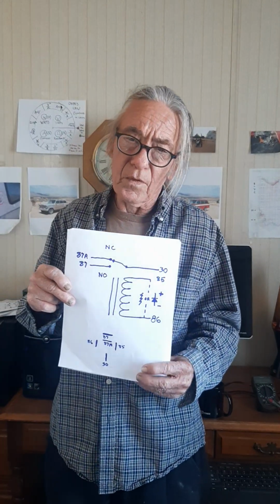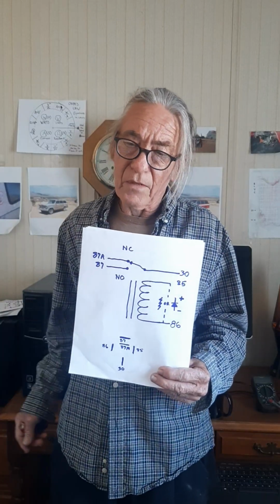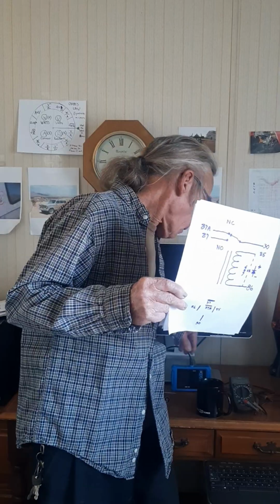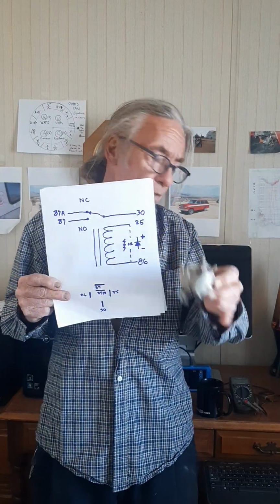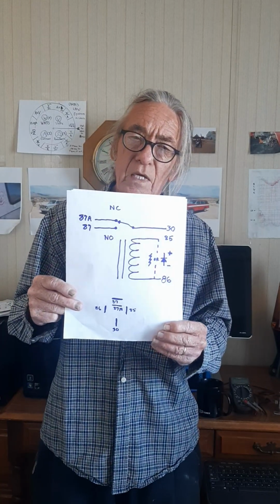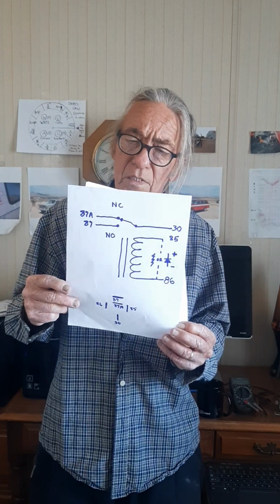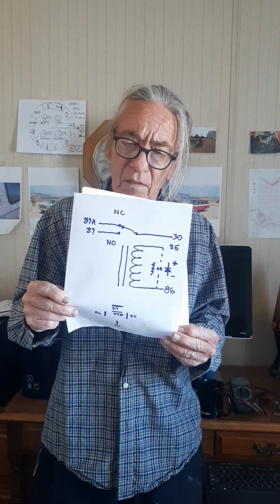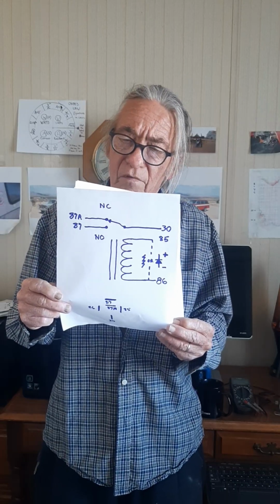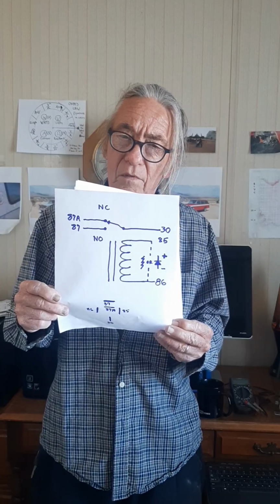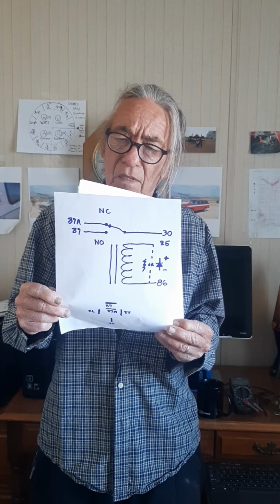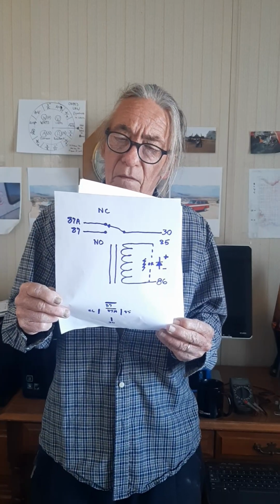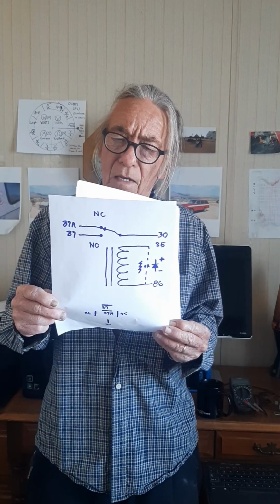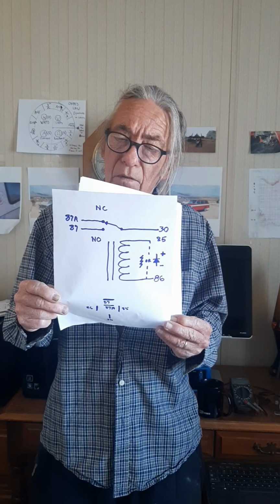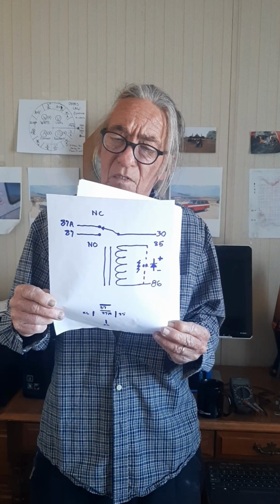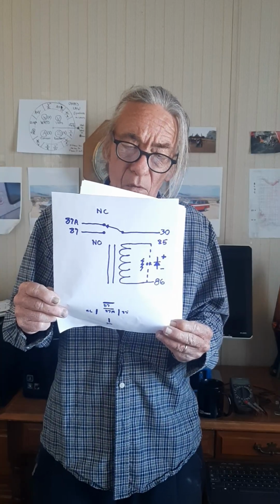Next is the solenoid, or relay. Relay is actually the correct term, but we tend to call the little ones relays, and when they get big like this, we call them solenoids. Electrically they do the same thing: they use a low current switch to switch a very high current, and that's what the contacts are. You'll notice there's an NC and an NO. Many relays will conduct in the closed position and have an NC terminal, or conduct in both open and closed, having both an NC and an NO terminal, or they can only function in the normally open position, in which case the NC pole is not there.